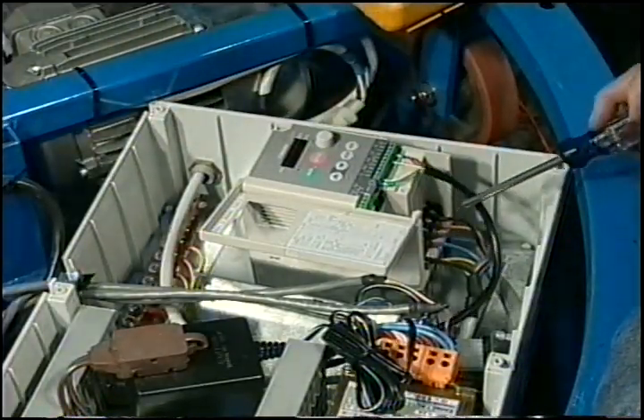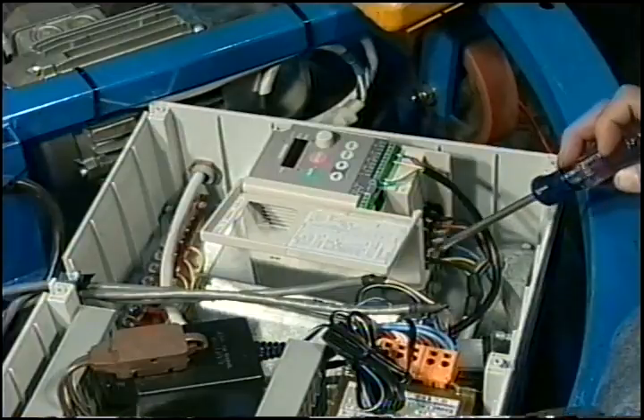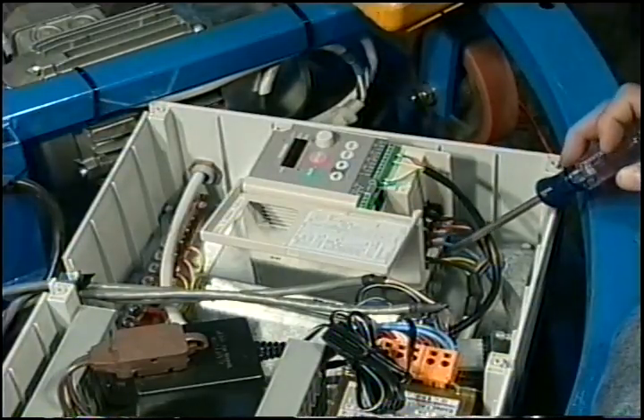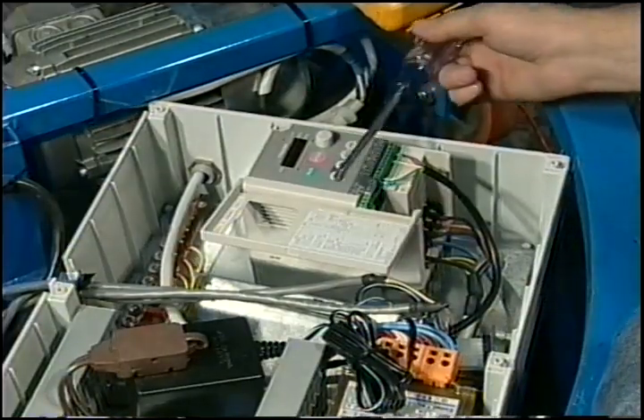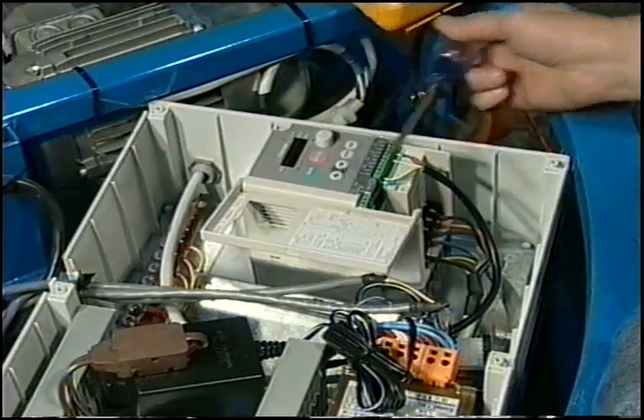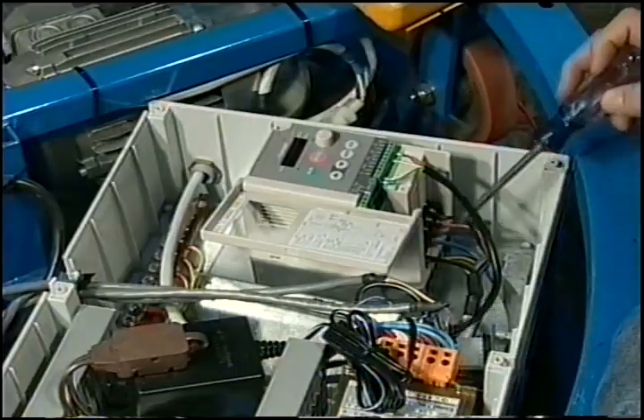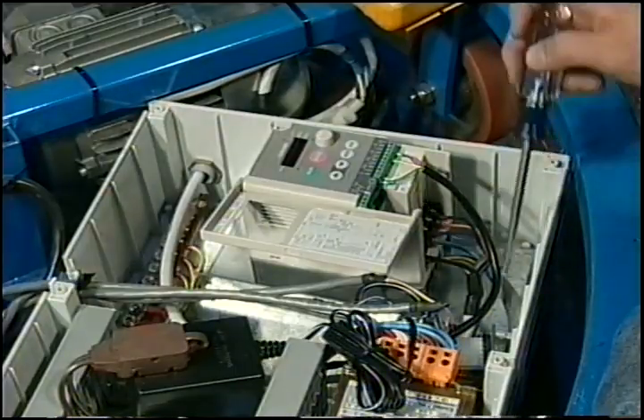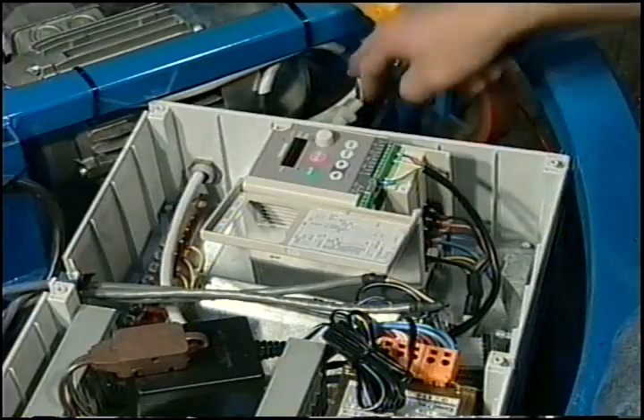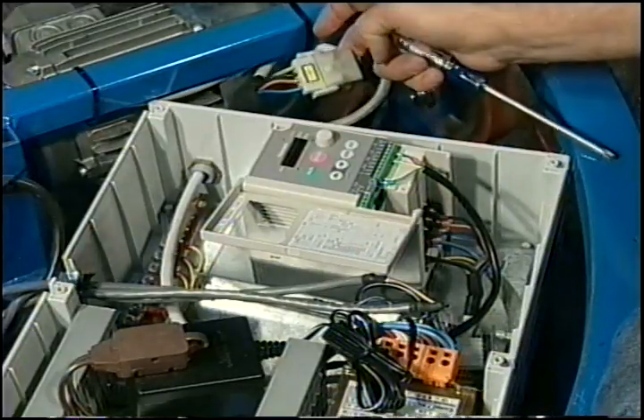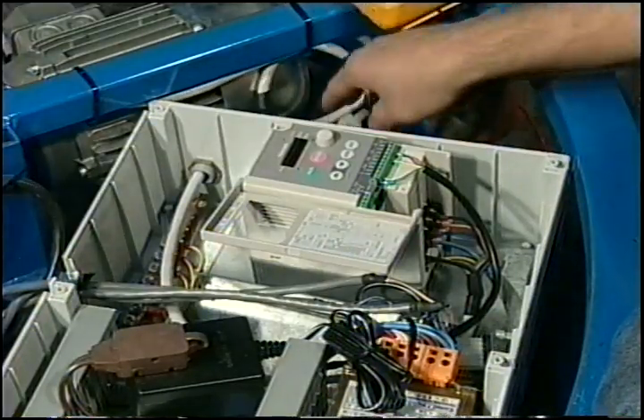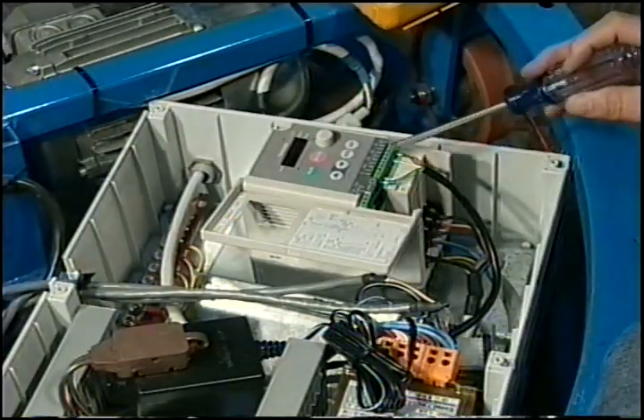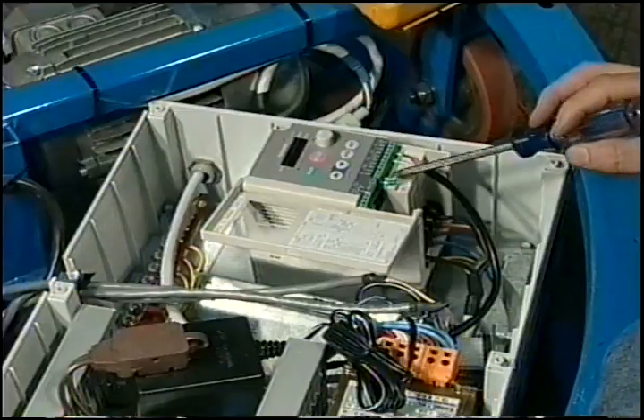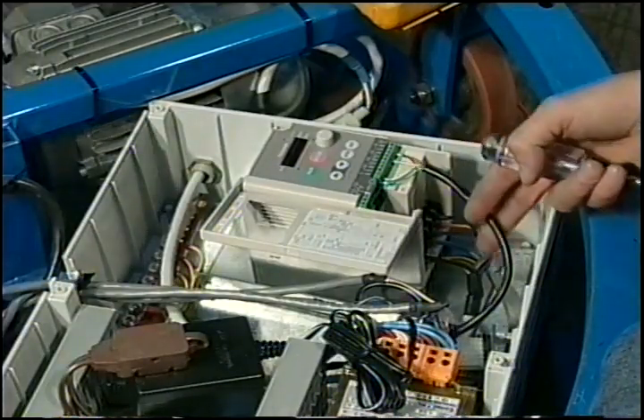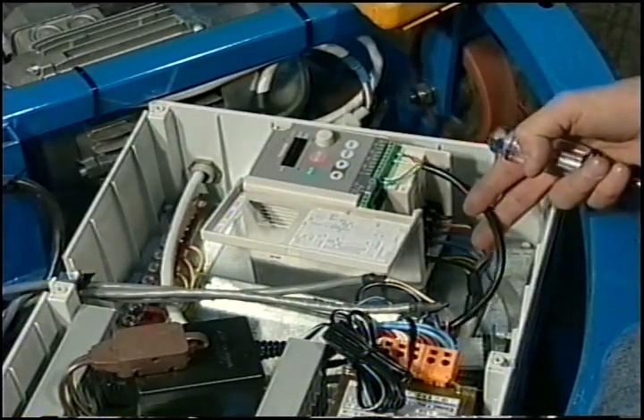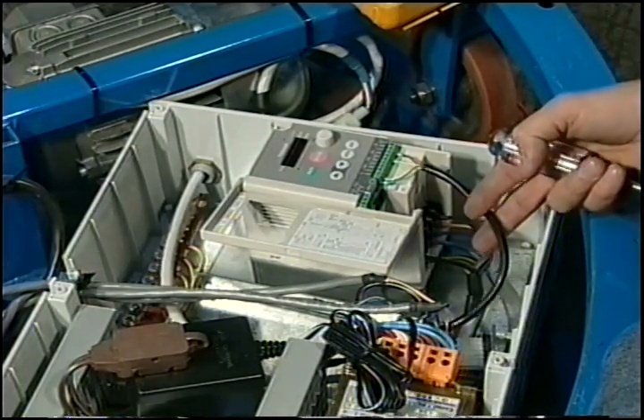You have terminals down on the bottom. The first 2 pins on the left are your power coming into the box. That's this 120 that supplies voltage to the terminal. And then these 4 wires on the right here are your 4 wires going out to your rotation motor. Same 4 wires that you find right here. Okay. The top terminals here, the green ones, they're labeled. These are the 4 wires that are going to your CPU board located just under your cache box.